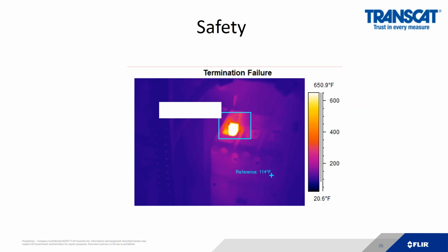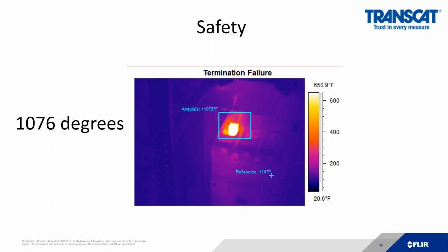If he moved that wire to get the clamp meter around it, he may cause the connection to have an arc flash because it is very close to melting down. I've blocked out the temperature because this target is very close to the melt temperature of aluminum. Does anybody know the melt temperature of aluminum? It's around 1200 degrees. In this case, this target is around 1076 degrees. That's why electricians are guided to wear PPE, but I would suggest the next step level up would be to also include a thermal imaging camera that can show you this problem before it happens.